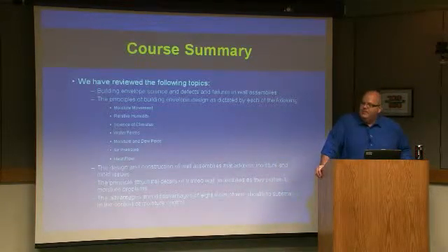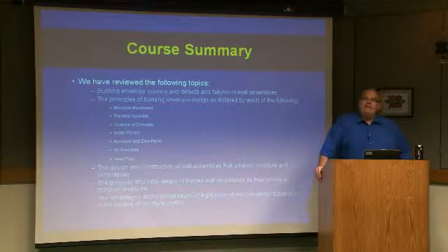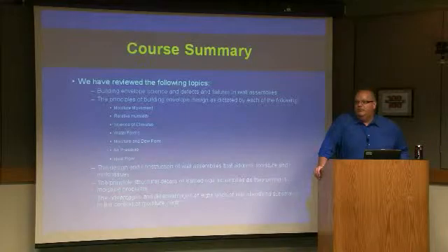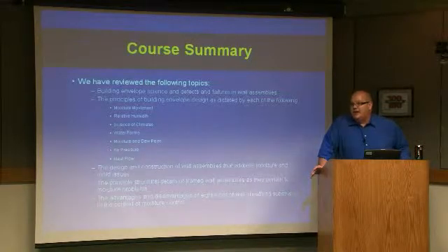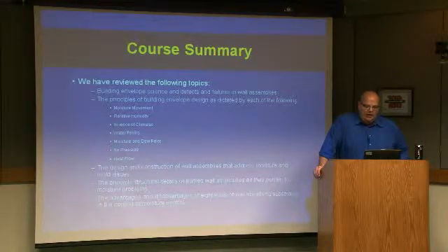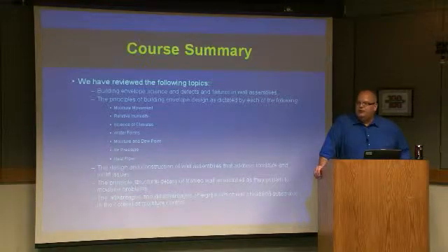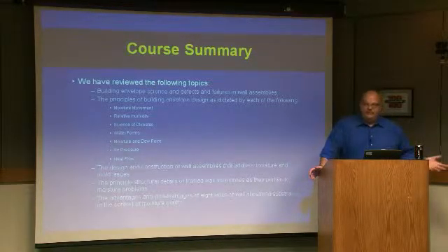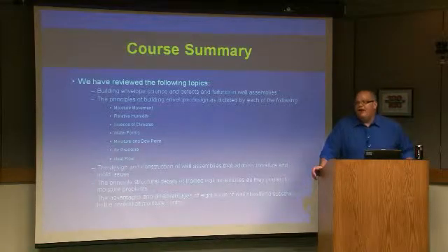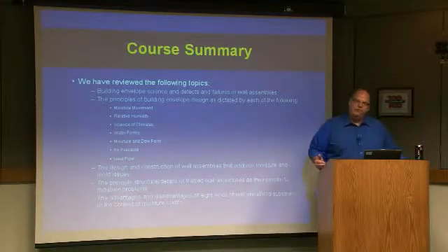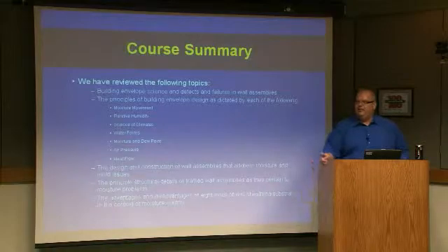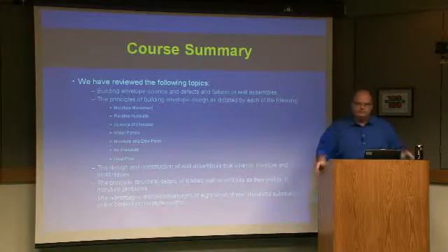So what's the point of putting poly across the kraft face batt? What it gave us was an interior air barrier. We didn't realize we were getting that. It hurt us in a lot of ways because it's too low a permeance. 1 U.S. perm is a vapor retarder by the old definition. A kraft face batt goes from around 0.7 U.S. perms up to about 3 U.S. perms in high humidity. It's right around that 1 range.